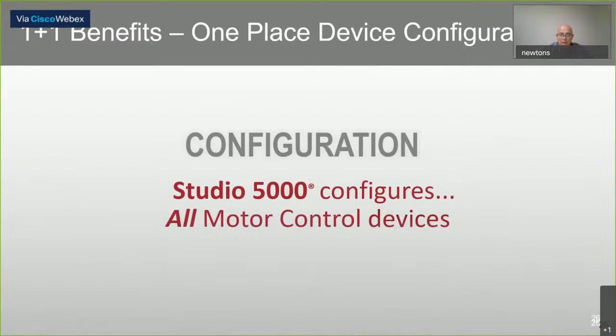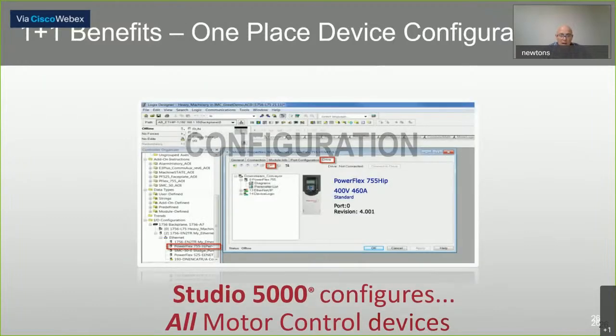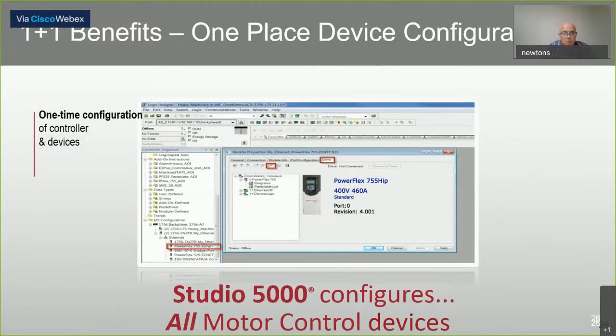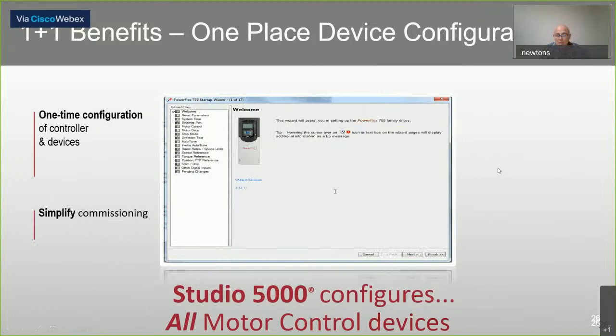The next benefit is again in Studio 5000, and it's one place, one configuration. Basically, all those devices can be added to the application, to the program, and all the parameters within that device can also be established and maintained in one place. So Studio 5000 has the ability to allow us to configure anything from a drive to an intelligent motor starter, or even to sensors. We can do this one-point configuration. It's configured there, and it's saved and maintained. So if it needs a backup or recovery, it's also done through Studio 5000. Obviously, this then simplifies commissioning and startup.